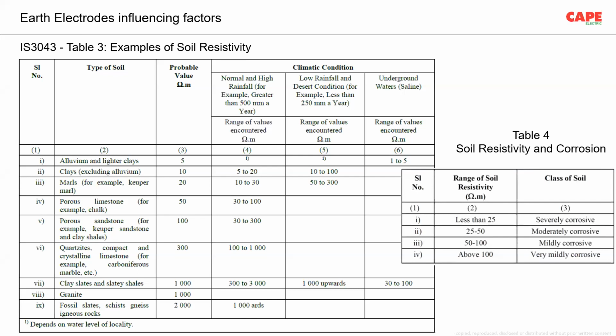In soils with low soil resistivities, let us say, for example, less than 25 ohm meter, the soil is severely corrosive. On the right side, you can see here, severely corrosive. That means in places where the soil resistivity is less than or equal to 25 ohm meter, you have to be very careful because the earth electrode can be eaten away very fast. It can corrode very fast. Then moderately corrosive, mildly corrosive, and very mildly corrosive. Anything above 100 ohm meter is mildly corrosive. What you should understand is that, of course, a low soil resistivity offers a low earth electrode resistance, but it increases the corrosion of your earth electrode.